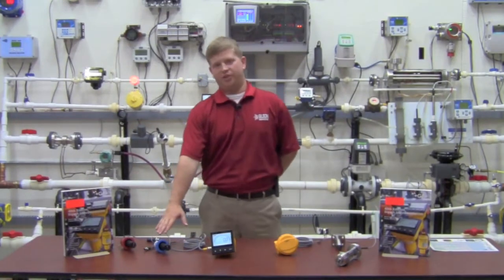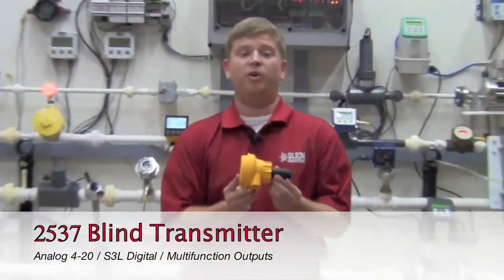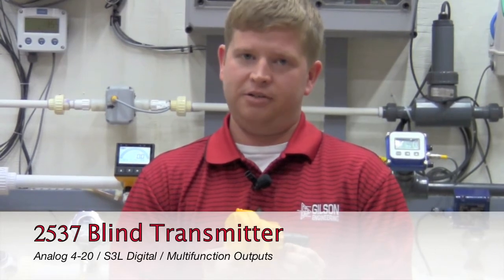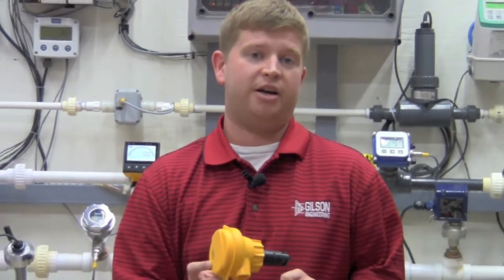Very similar to the 2536, Signet offers a 2537 paddle wheel flow meter. This unit comes blind, but it does offer a different output option. You can do 4 to 20 output, digital S3L, which is Signet's proprietary communication, or a multi-function output.